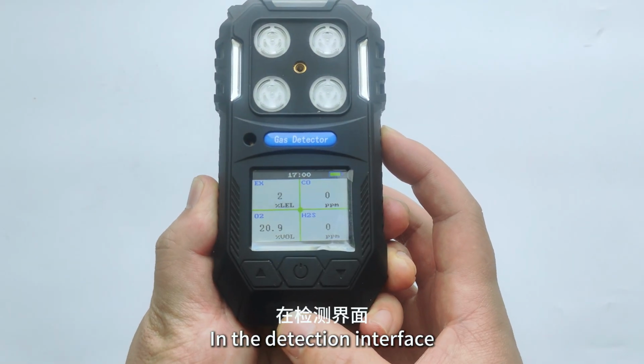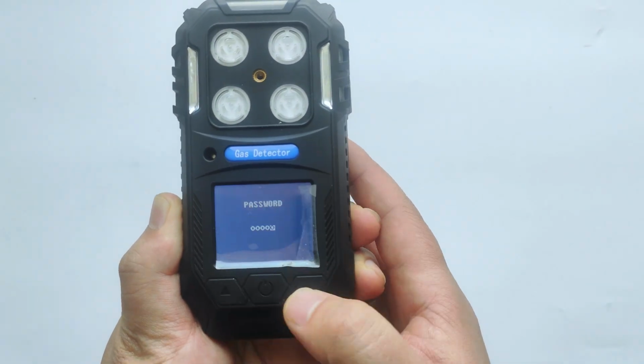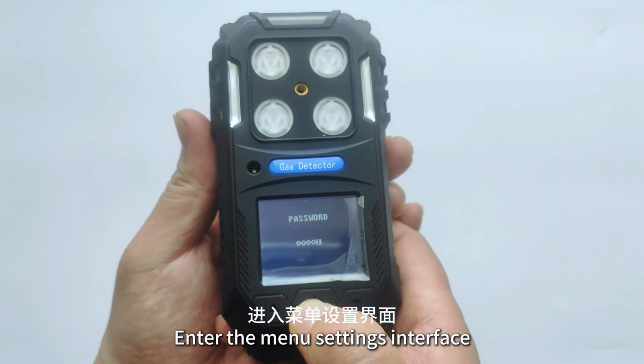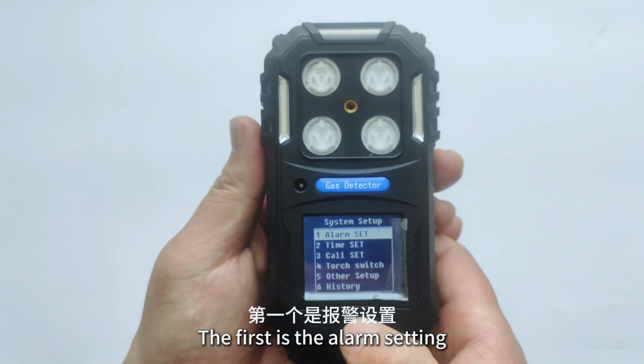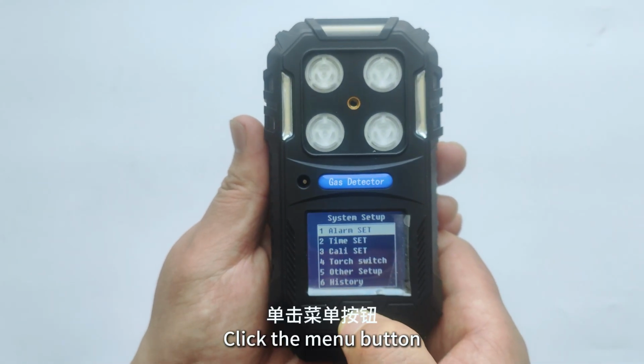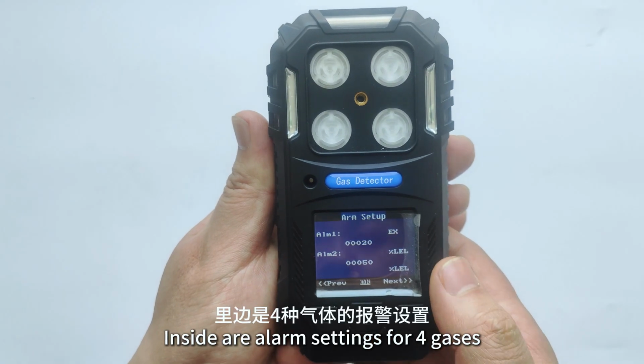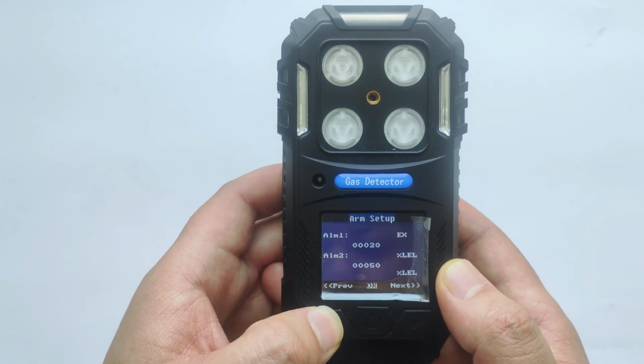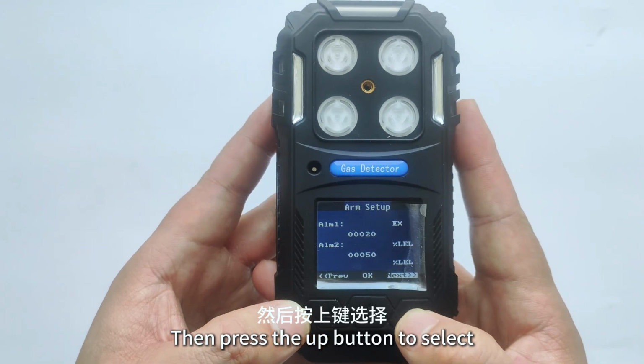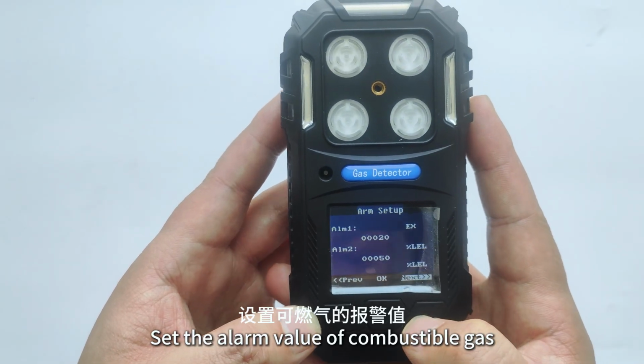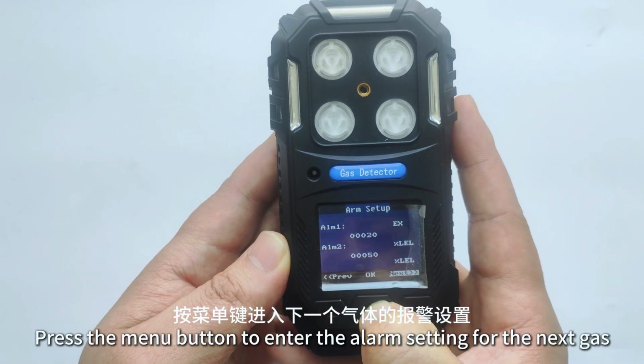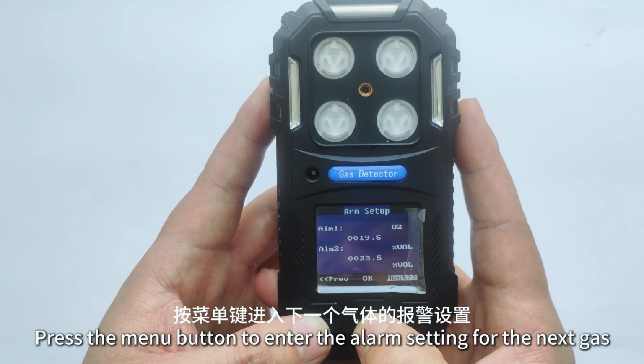In the detection interface, click the menu button in the middle. Enter password 1. Enter the menu settings interface. The first is the alarm setting. Click the menu button. Inside are alarm settings for 4 gases. Then press the up button to select. Set the alarm value of combustible gas. Press the menu button to enter the alarm setting for the next gas.